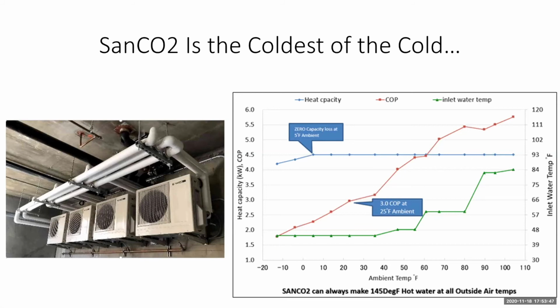And so this is producing exactly its rated amount of hot water, even as its COP is dropping. And its hot water production starts dropping only at about 5 degrees Fahrenheit. So it's rare that you're going to have any issue at all with hot water delivery. You should be able to continue to produce all the way through the most challenging of weather, just knowing that it's going to be less and less efficient.